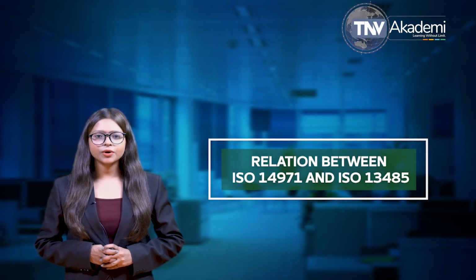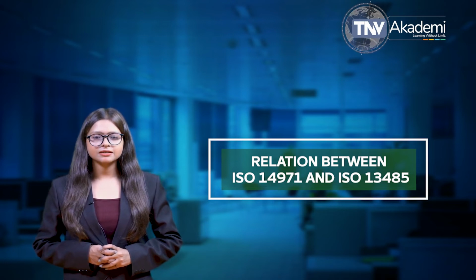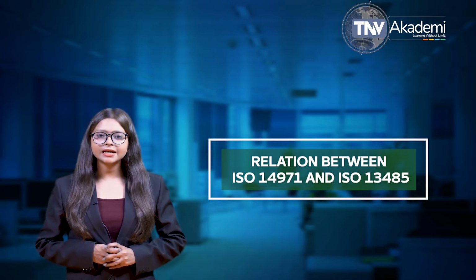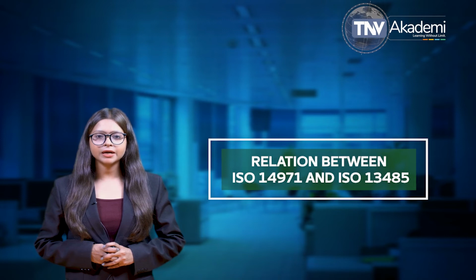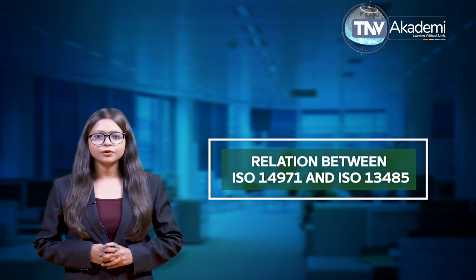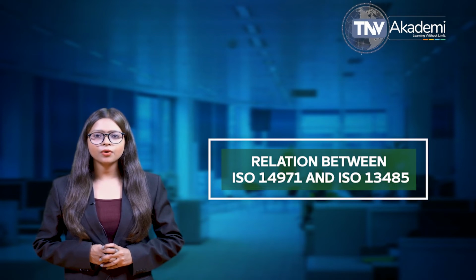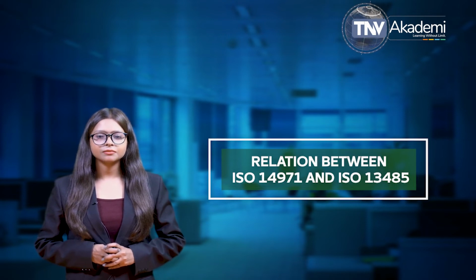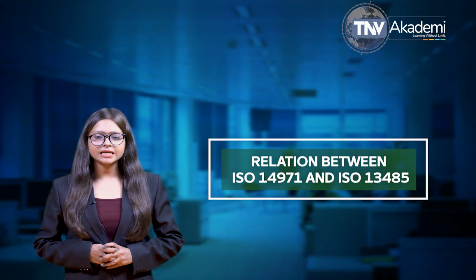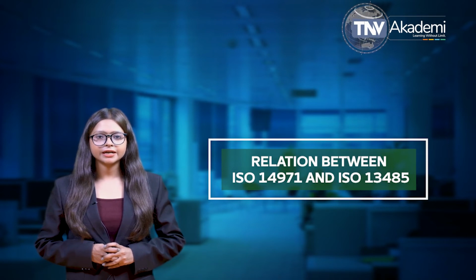ISO 13485 is focused on regulatory and customer requirements for medical devices, as ISO 13485 requires risk analysis and record keeping pertaining to any risk. ISO 13485 looks to ISO 14971 for guidance. ISO 14971 is more detailed when it comes to risk management requirements.